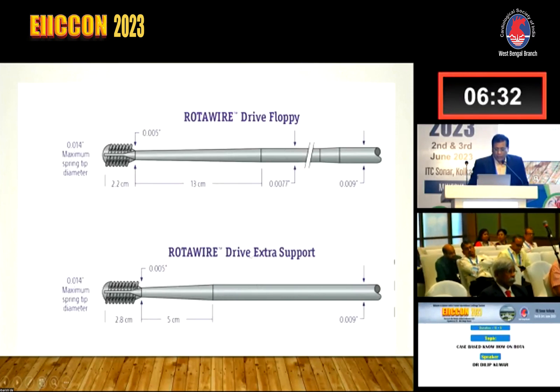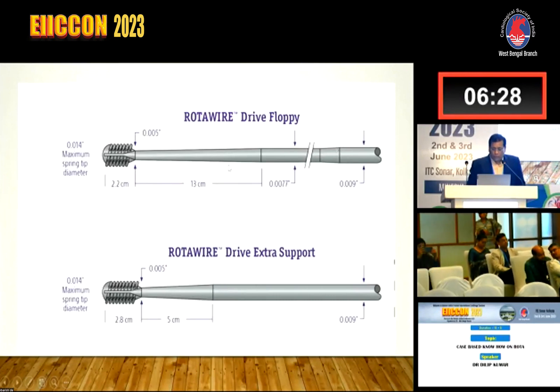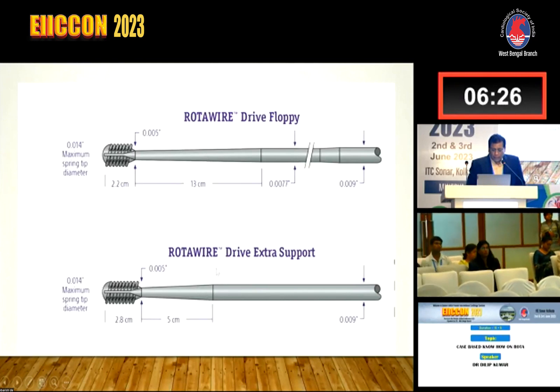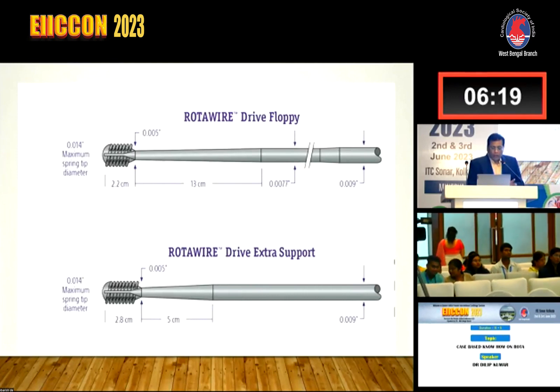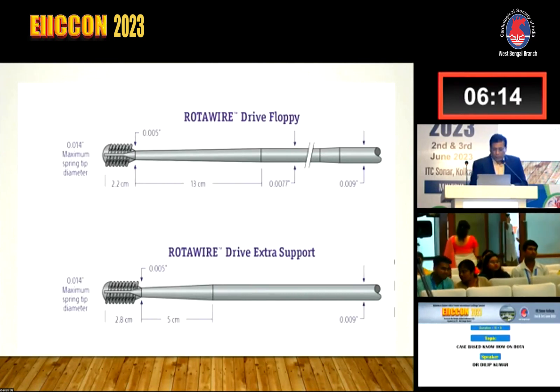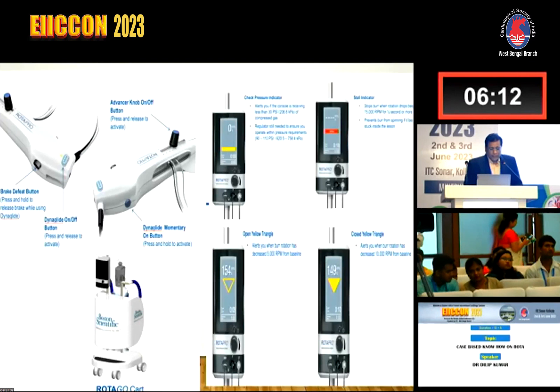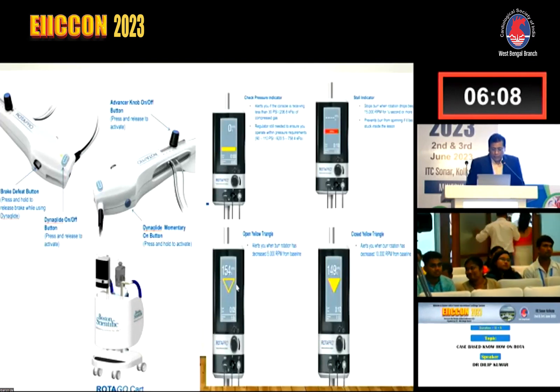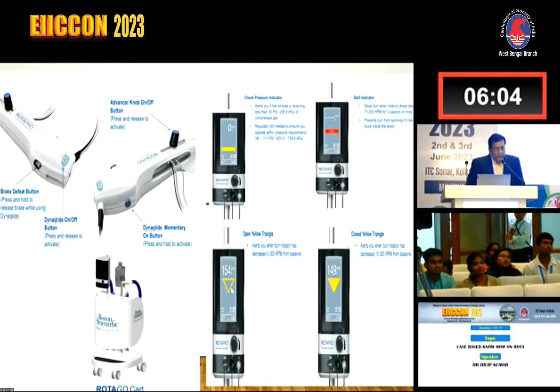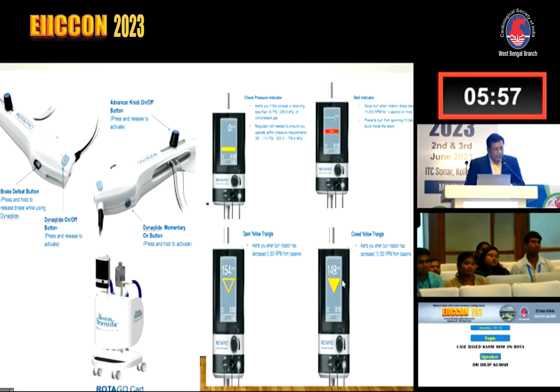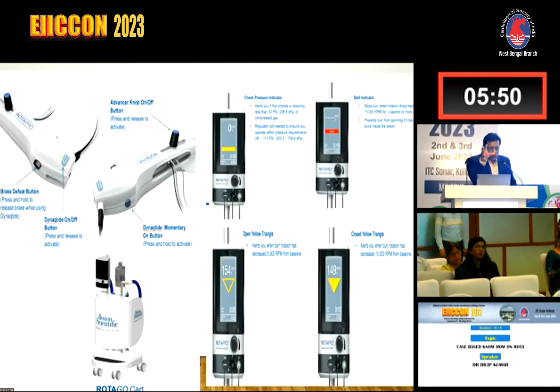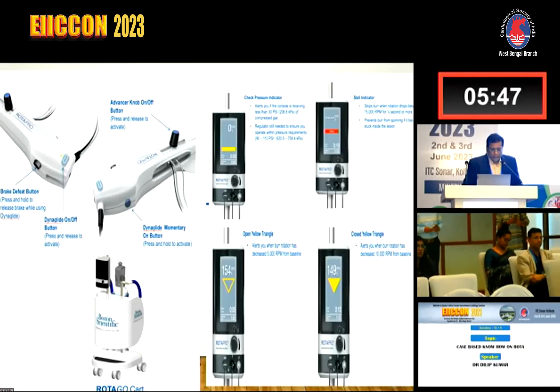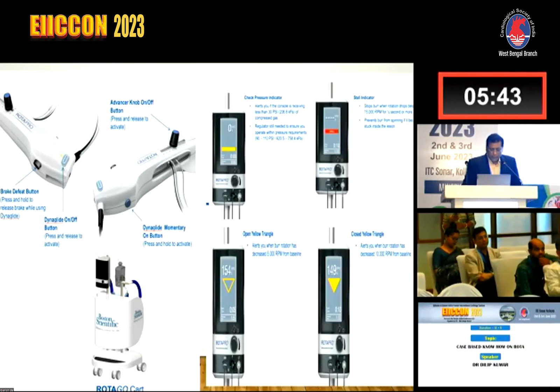The rota drive extra support wire has a uniform 0.009 thickness to 5cm, then tapers directly to 0.005 - there is no transition through 0.0077. In rota pro, the yellow triangle indicator tells you that rotation has decreased by 5,000 rpm from baseline, and a solid triangle indicates 10,000 rpm decrease. This is a visually attractive system right in front of you, and it's a really good experience to use rota pro.